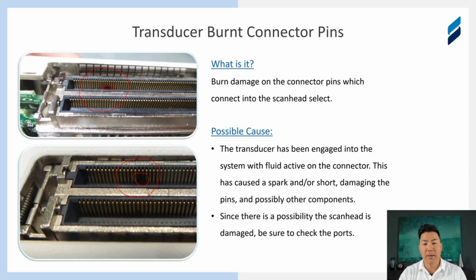But again, I think it just takes some education for the sonographers. Make sure those connectors and electronics are all dry. Don't put anything wet on them. It can be accidental sometimes. Actually, most of the time it's accidental. Nobody tries to put water in here, but hey, it happens. You have gel, and it's a common practice, you have to use gel to scan, and things happen. So when you see this, your red flag should go up right away to go check that system as well, and make sure that there are no burnt pins on the other side.